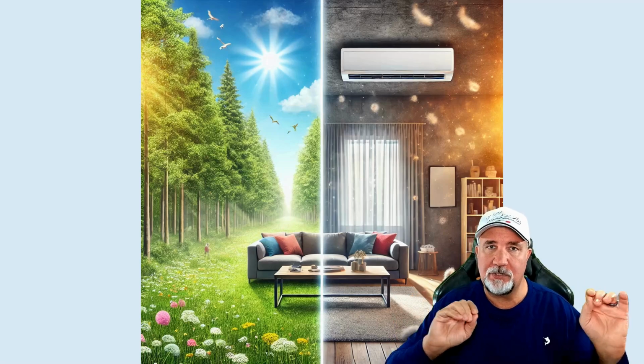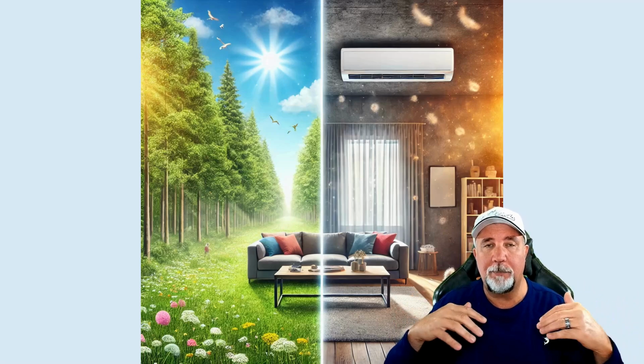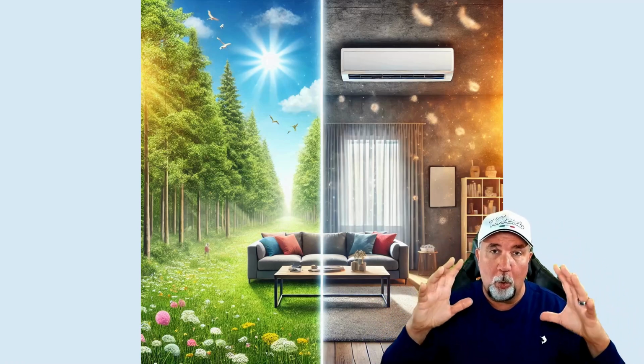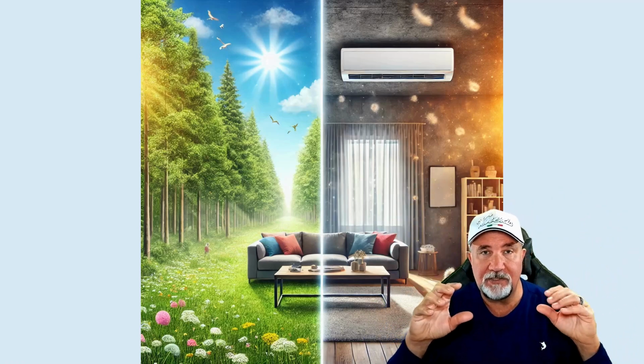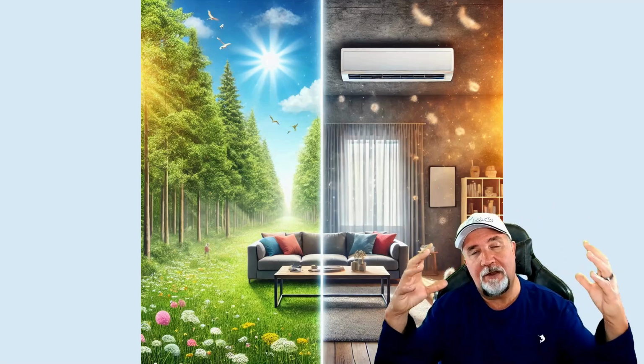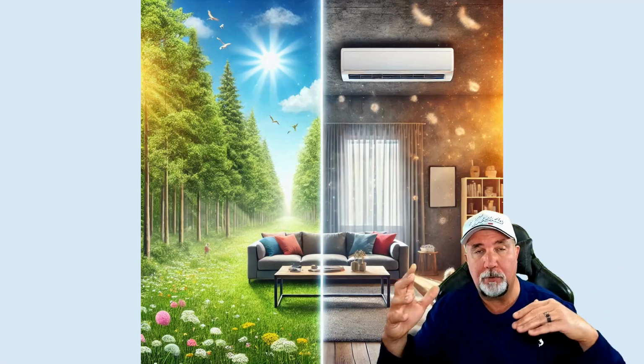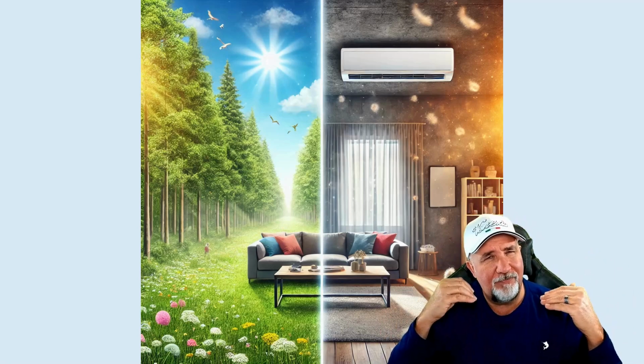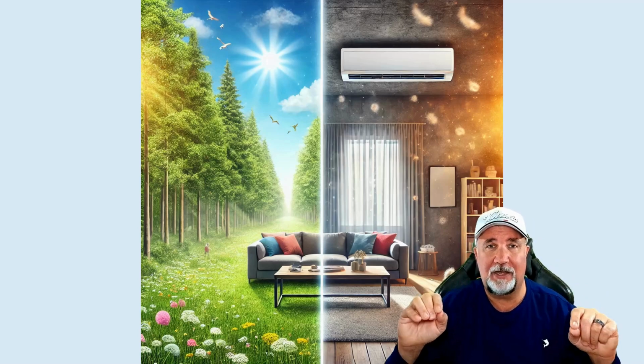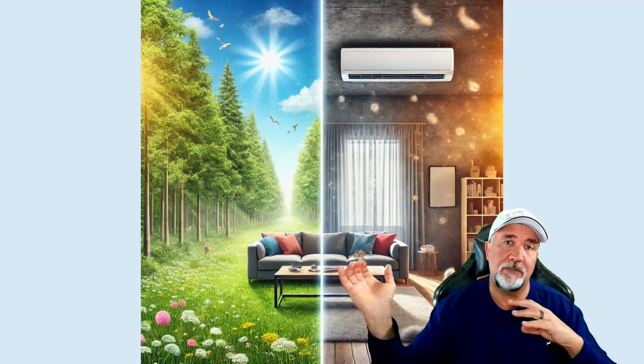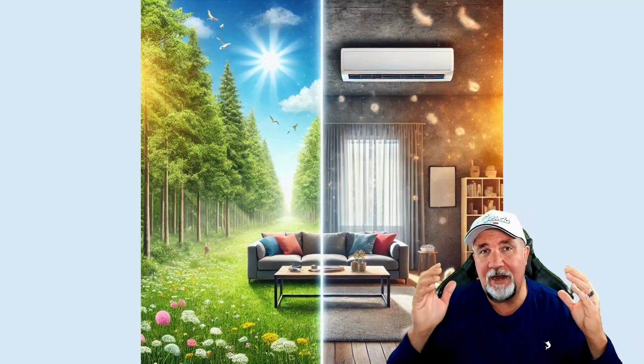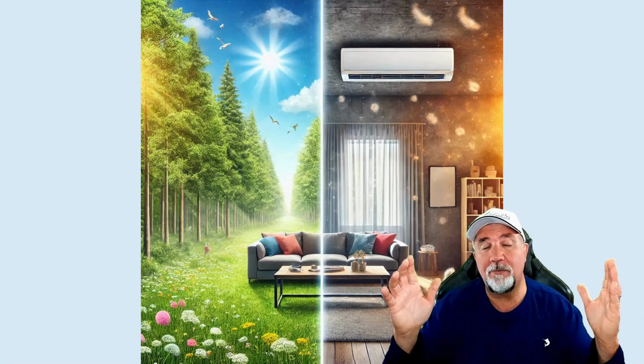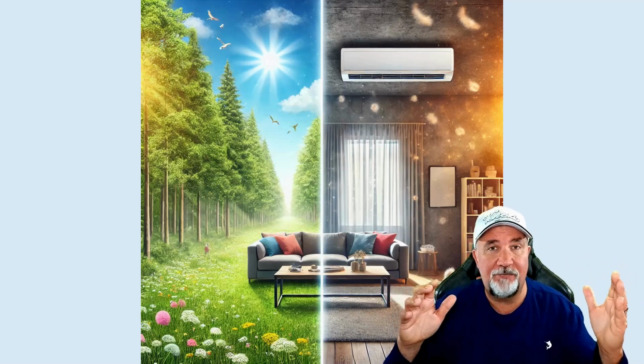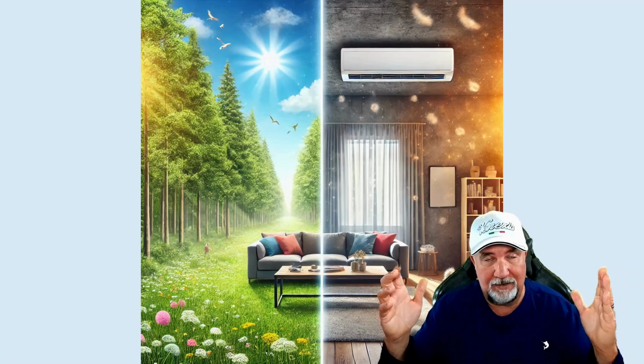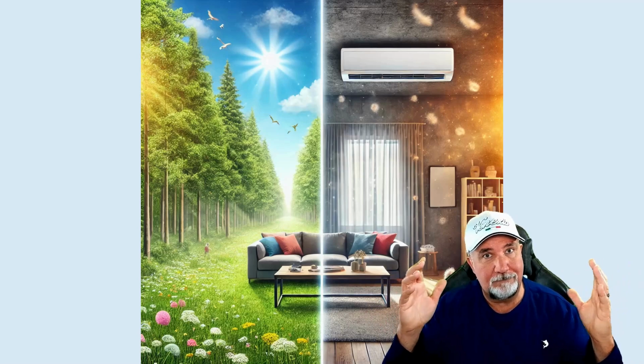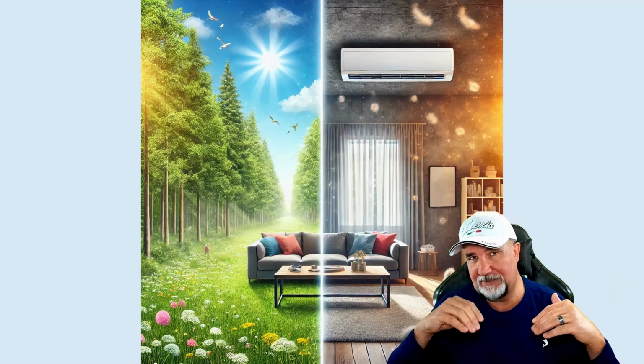Most of the time, most UV lights are there to help shine on the coils and the immediate part of the duct system to help clean and reduce particles and pollutants in that area. But very few, if any, UV lights are good enough to cleanse the air as fast as it's going through. Air is going through that air handler at anywhere from 350 to 1,000 feet per minute, and most of our residential UV lights can't work that quick.